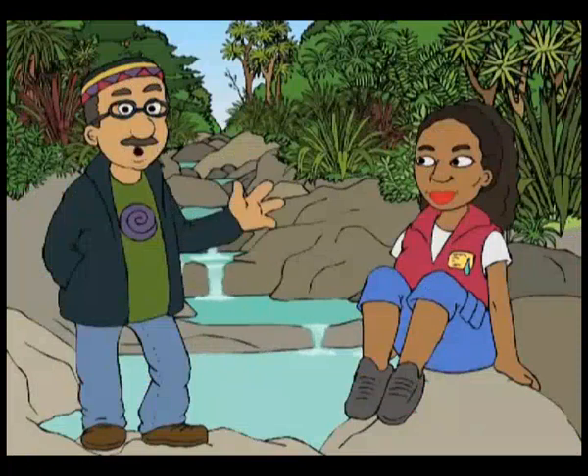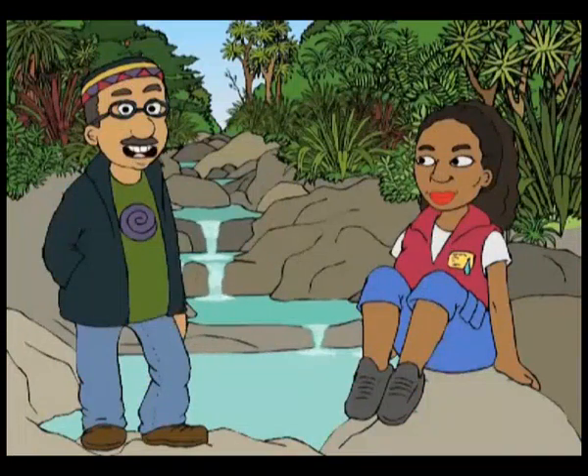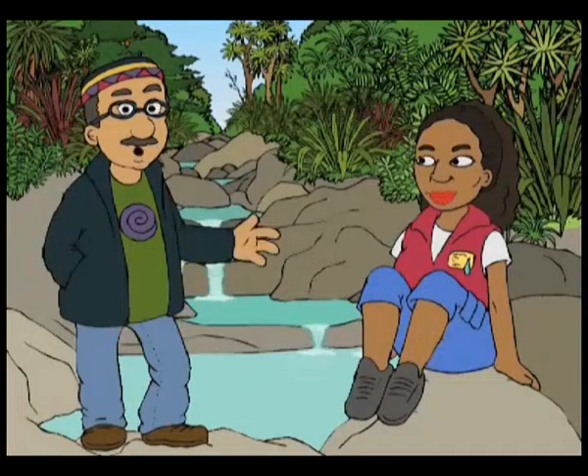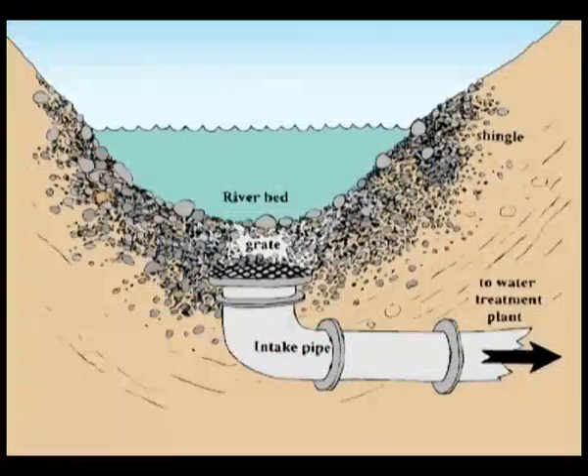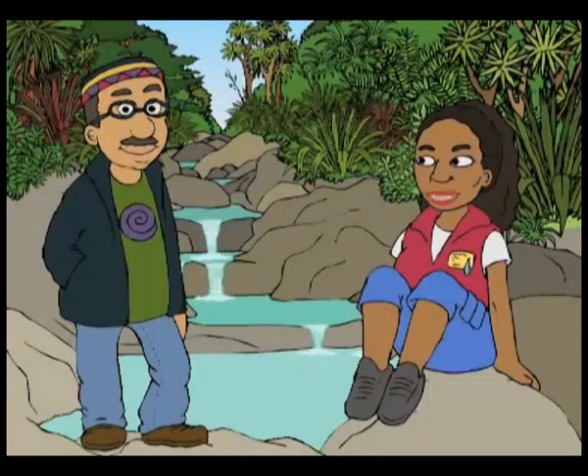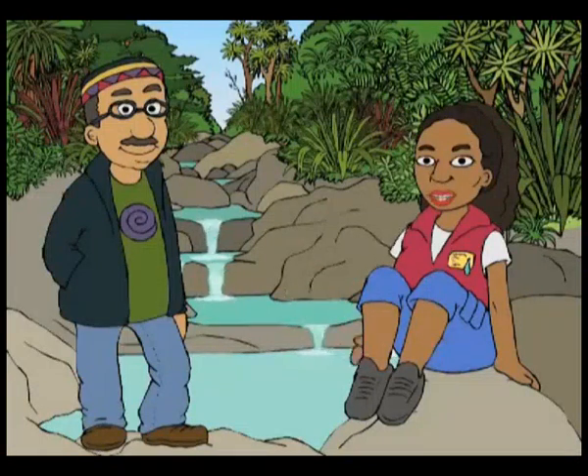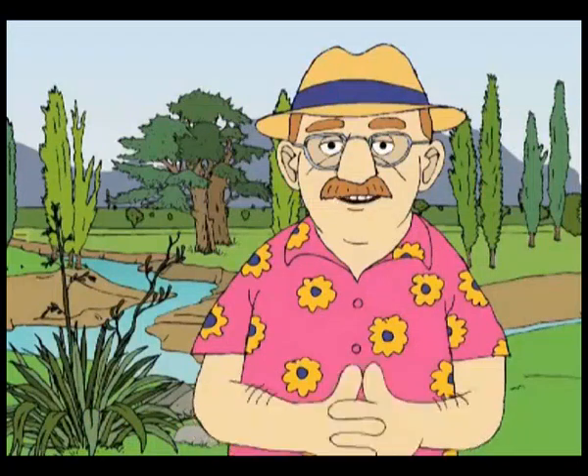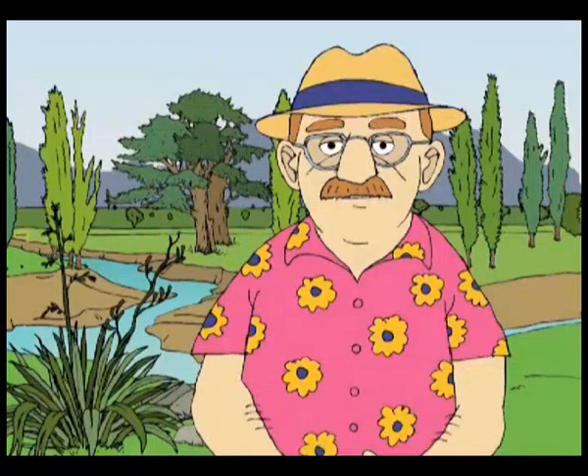Here we are at the stream — this is where we get our water supply from. We want to eliminate potential hazards from getting into our water supply, so obviously we don't just stick a pipe in and pull the water out. The intake pipe is actually a few metres below the river bed, so it's filtered by the shingle before we get it. That means we don't get leaves and dirt and fish in the water tank — nice clear water. And if we reduce the level of contaminants in the water we take, then the less we have to remove or inactivate later. Managing the catchment area is exceedingly important because you can reduce the amount of contaminants even before the water is collected.